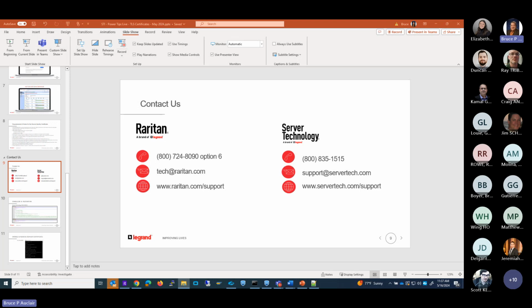So you could do similar to what I did using a host name instead of an IP address. You could include the IP address as a subject alternative name as well, in which case you could point the browser just using HTTPS with the IP address. So it's up to you, but yeah, it is generally much more flexible to use wildcard certificates. You really don't need to keep track of which certificate gets installed, or have a different certificate for every PDU.